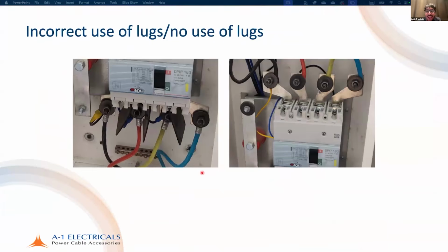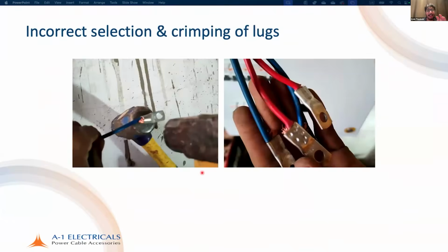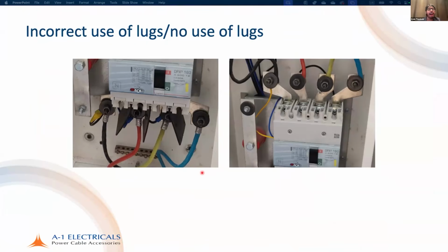So, very important, select the correct type of lug. Make sure that the class is relevant for your application. And when you are using a crimping tool, the die and the lug have to be dimensionally compatible. Otherwise, there is no point. And again, these are requirements in IS 732, and we know that non-conformity to these requirements is punishable according to the CEA regulations and the Electricity Act.